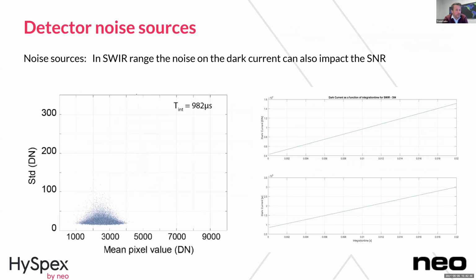But if you move into the shortwave range, which is from 950 nanometers to 2,500 nanometers, you actually have quite a big impact from dark currents. So dark current is changing, if you see here on the top right curve, quite a lot with exposure time. And basically you will have noise, photon noise on top of your dark currents, and you will have that the dark current increases linearly, right, with your exposure time, eating up your dynamic range of your detector. So for SWIR sensors, that needs to be taken into account when you calculate your SNR.